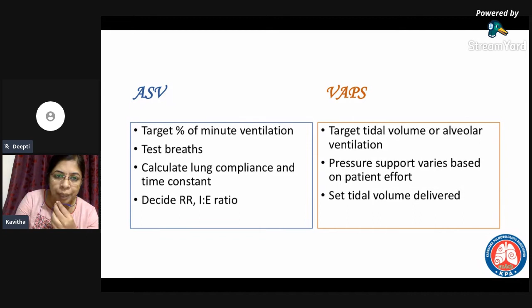Whereas in volume assured pressure support, as the name itself suggests, you set the tidal volume. That tidal volume will be assured by the machine, and the pressure support will keep varying based on the patient effort. But the tidal volume that you have set will be rendered at whatever pressure support is required. So if the patient is breathing less, the machine will give more pressure support. If the patient is putting in more effort, the pressure support will decrease. So the tidal volume that you have set will be delivered. So these are the basic principles of how the PAP devices work.